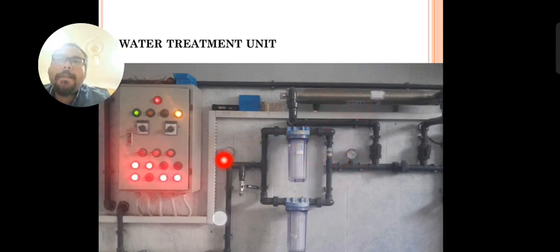This is the pressure manometer, responsible for monitoring the bacterial filter. This pressure reading must be equal, with no more than a 2 bar difference between the two digits.